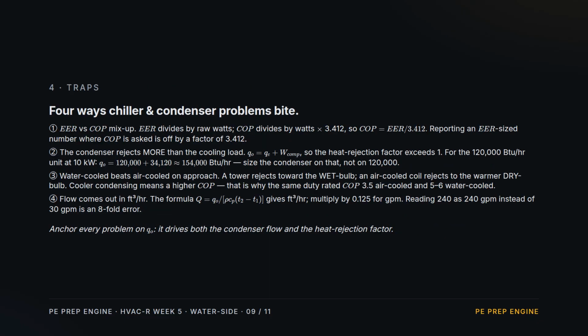Traps. 4 ways this bites. 1. EER versus COP. EER divides by raw watts, COP by watts times 3.412. Hand back the wrong one and you are off by that factor. 2. The condenser rejects more than the cooling load. Our 120,000 BTU per hour unit drawing 10 kilowatts rejects about 154,000. Size the condenser on that, not on the capacity. 3. A tower rejects toward the wet bulb, an air-cooled coil to the warmer dry bulb. Cooler condensing is the entire efficiency case. 4. The flow formula gives cubic feet per hour, multiply by 0.125. Reading 240 as GPM is an 8-fold error.